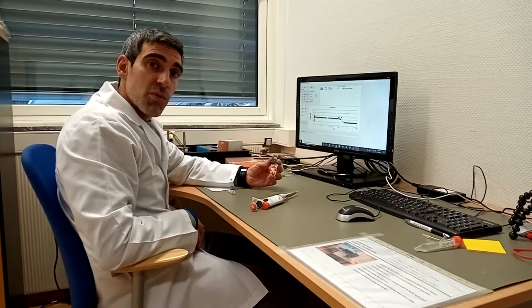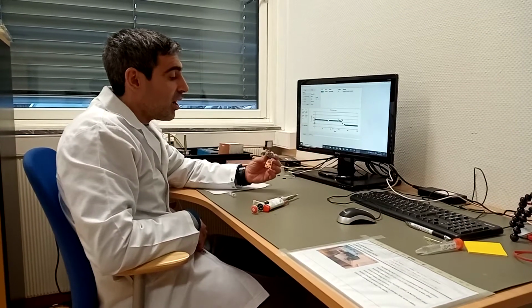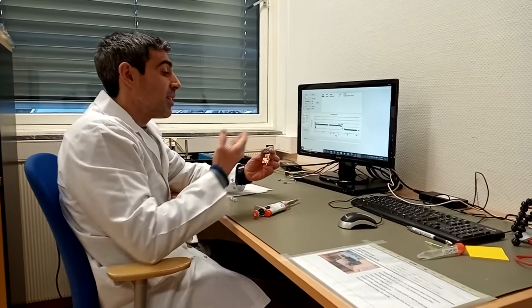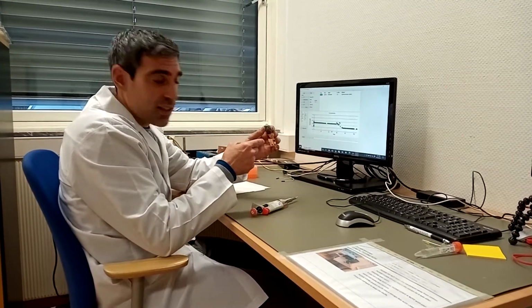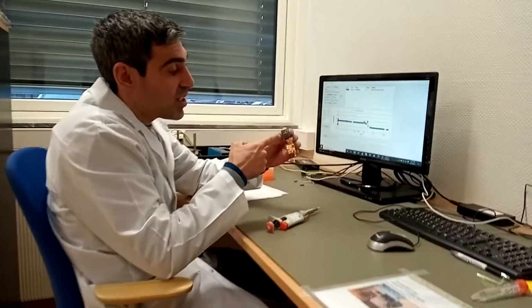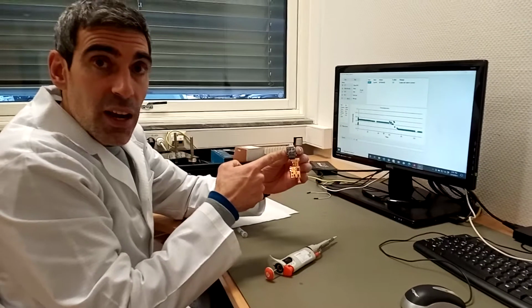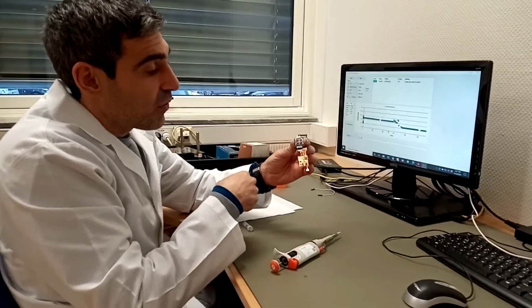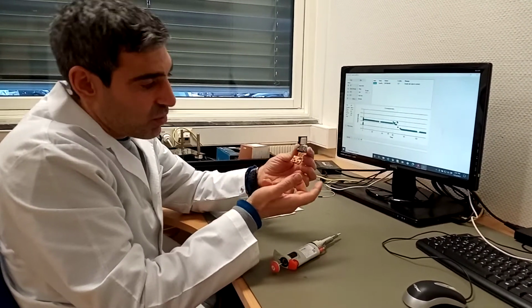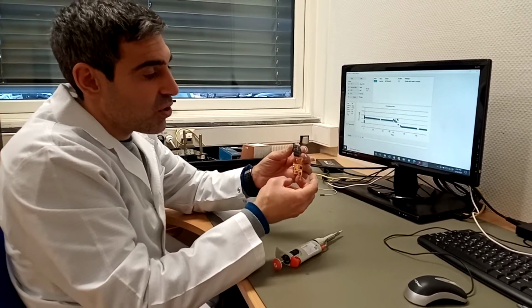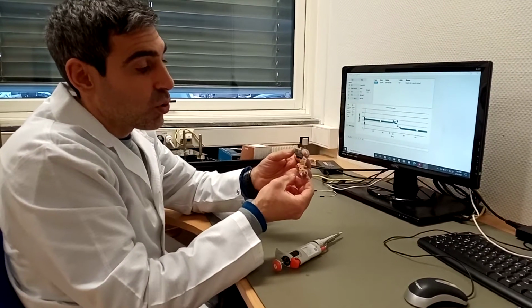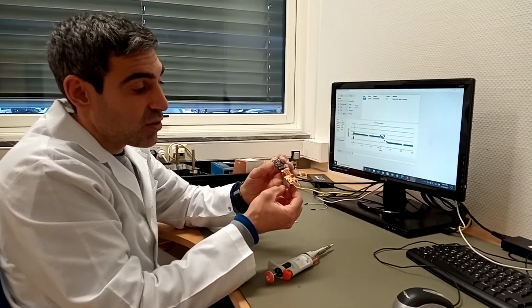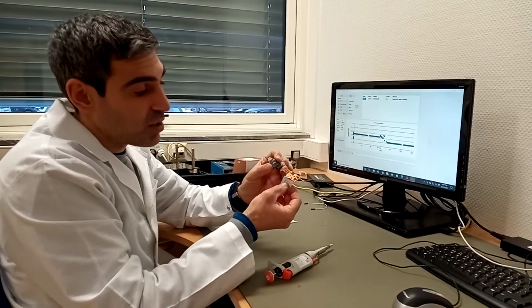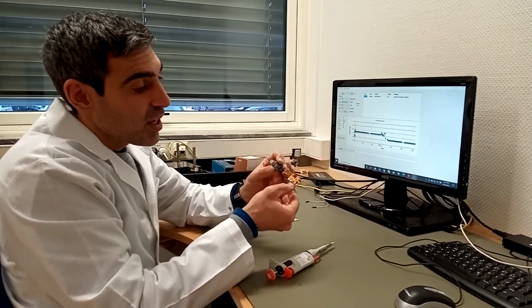Today I will do a small demonstration on how to test our EC Flex together with our ZP microneedle airway sensor. So the first thing you need to do is to grab one EC Flex. You'll need to power the EC Flex with about 3 volts. In this case I have soldered the flexible battery to it.